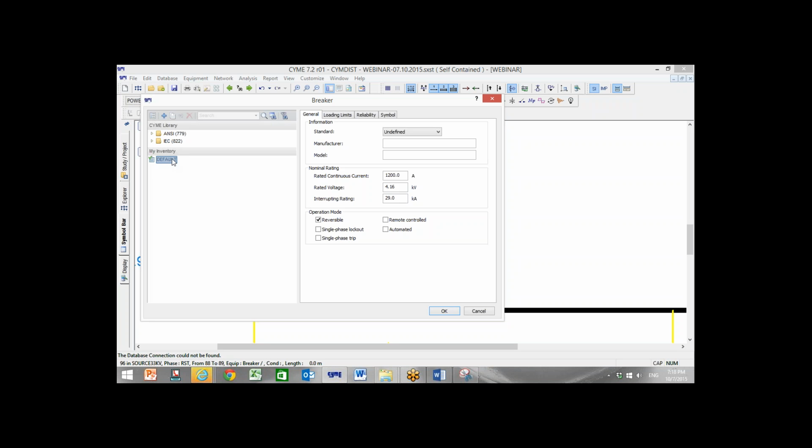So for example, now if we have 2200 and the maximum load is something like 2600 ampere, we go to a 3000 rating of ACB. And the short circuit rating is also very important for us. Okay, let's do it. I can also use the CYME library, but I don't want to use the CYME library. It's a library for ANSI and IEC. I don't care about it.